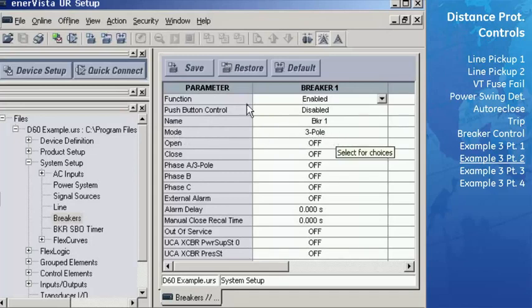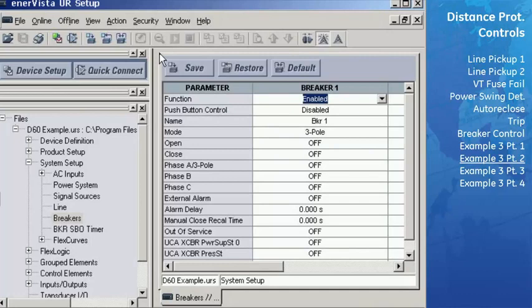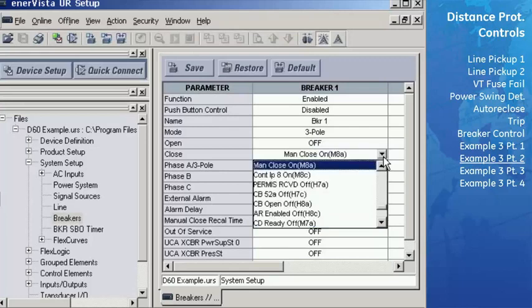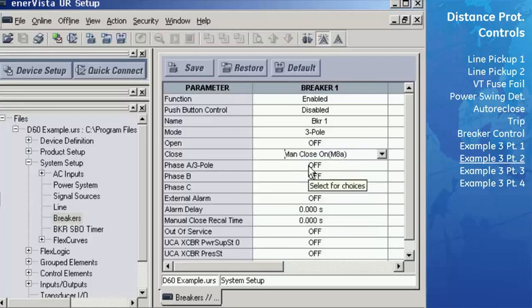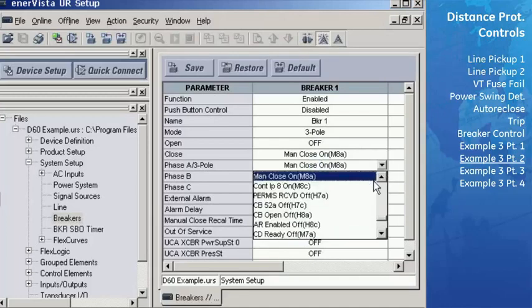For this example, contact input M8A will be used for a manual close. No inputs are available to manually open the breaker, so keep the open setting as off, and change the close field to contact input M8A. Additionally, the circuit breaker open signal 52A will be wired to contact input H7C. This will be used by the breaker control to read the status of the breaker. Therefore, set phase A/3 pole to contact input H7C on.